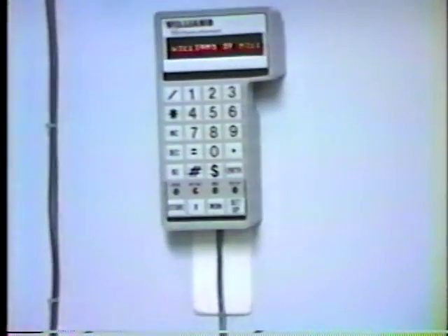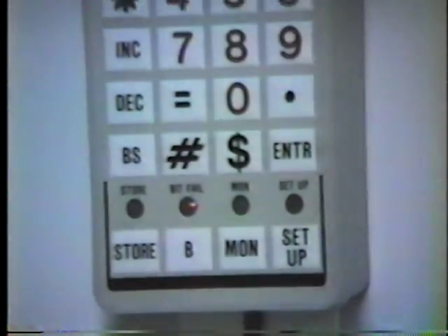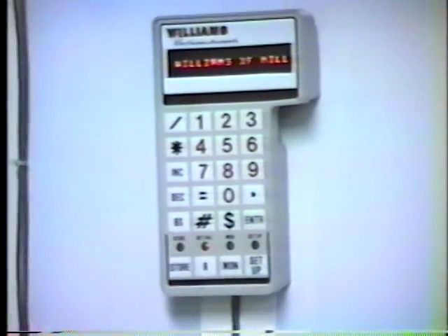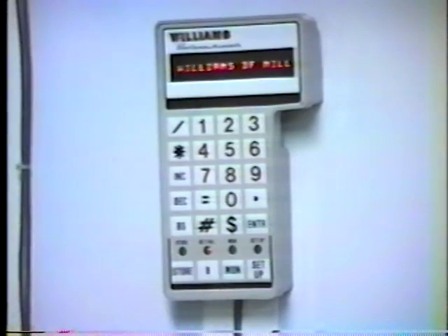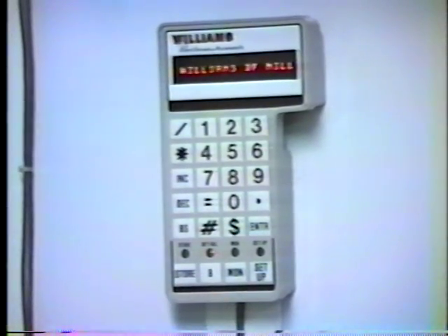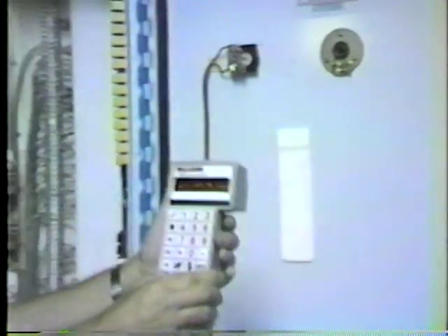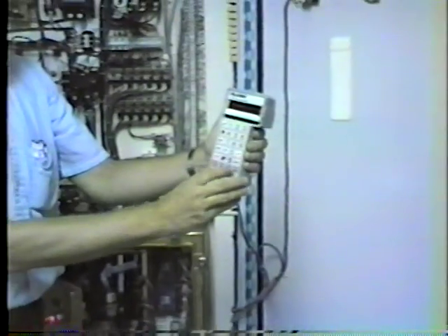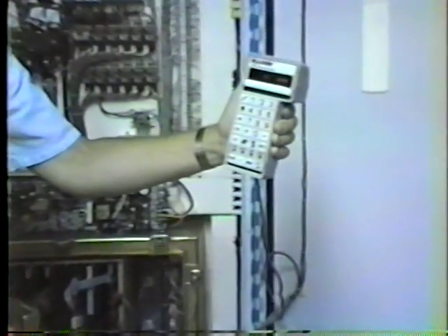Turn it on, please. Now, you can see that we've got the BIT failure light. We should also point out that we did not get pulverizer ready to start. Now, you cannot go forward any further, is that correct? That is correct. We have to go to the handheld terminal and see what failed. Would you do that? The built-in test is done at location 99. We have to go to the setup mode.